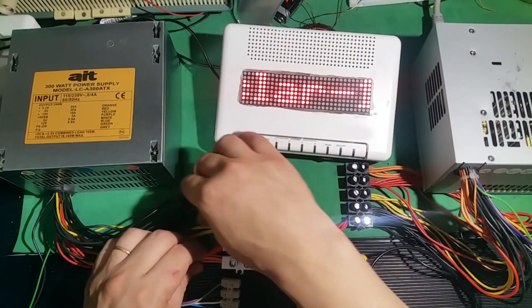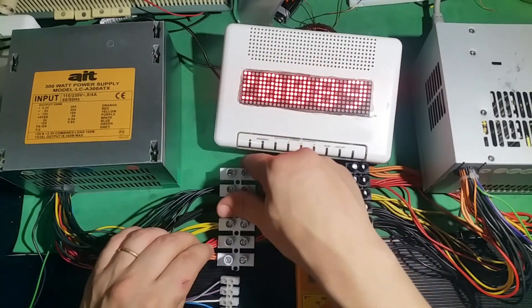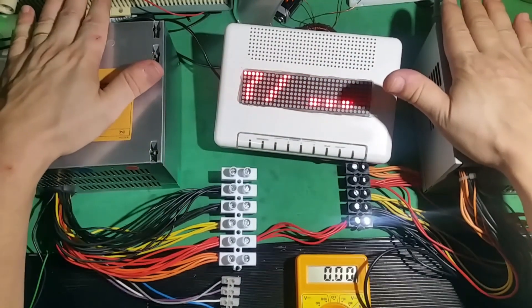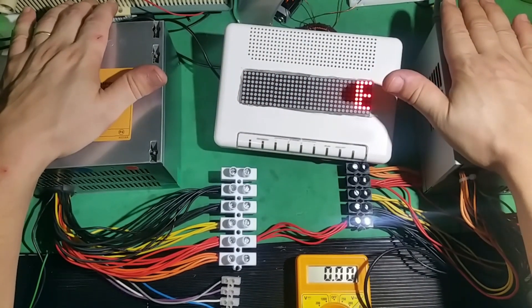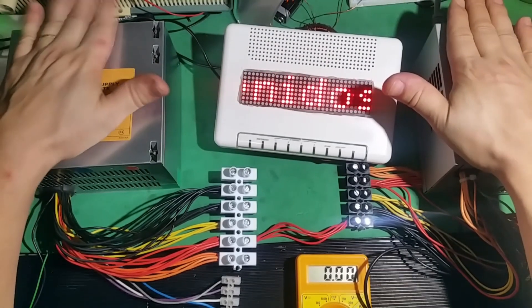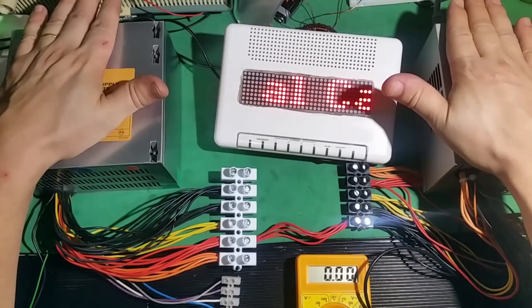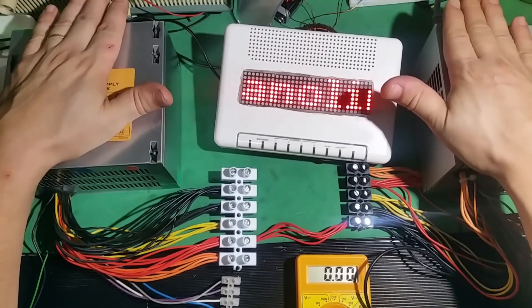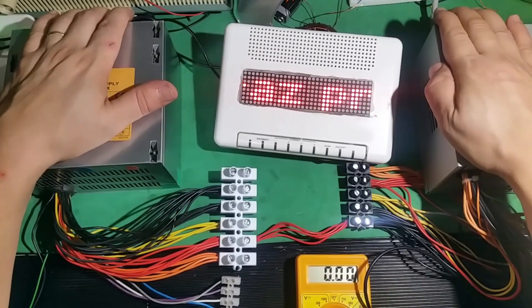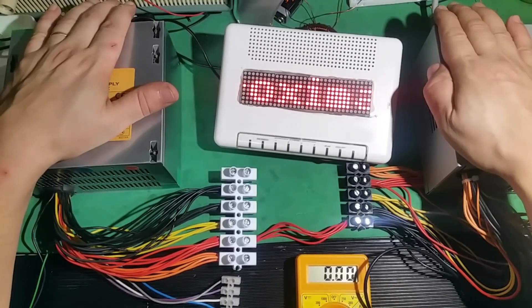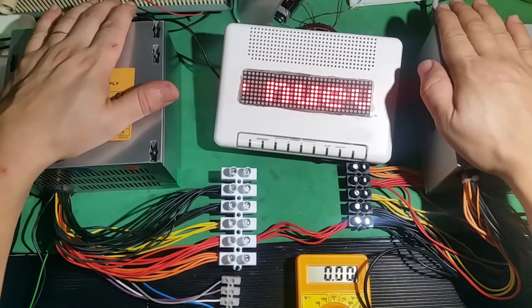As you see, it is possible to connect two power supplies in series with proper precautions. That said, the chassis must never be joined. The grounds must never be together.